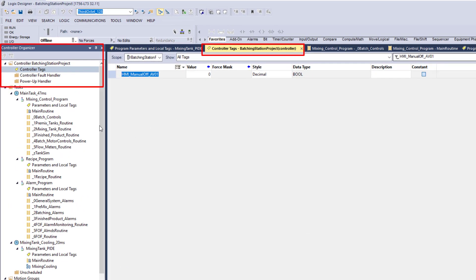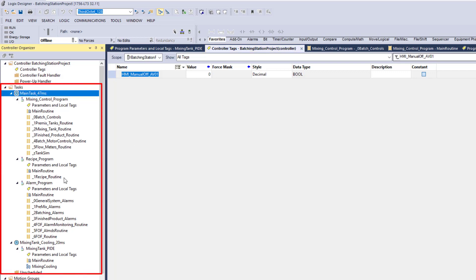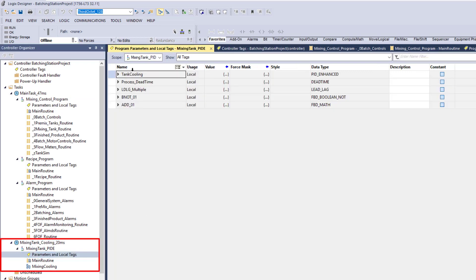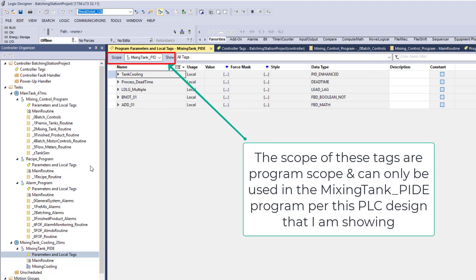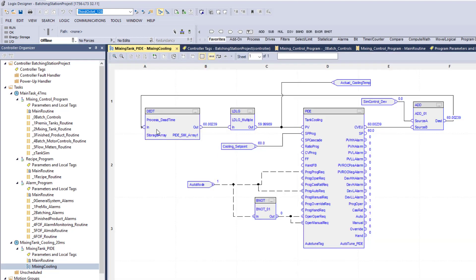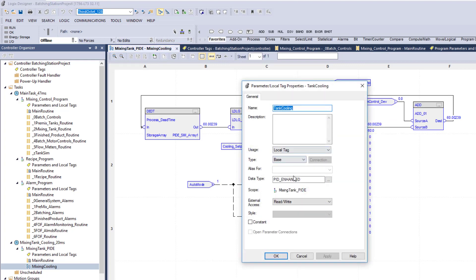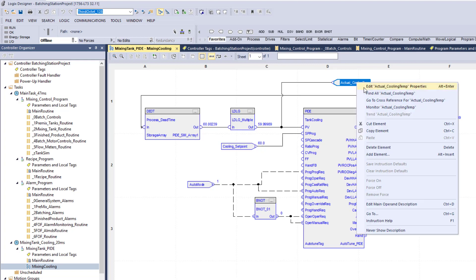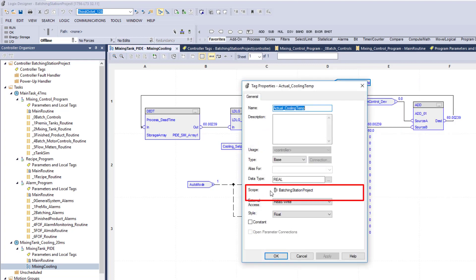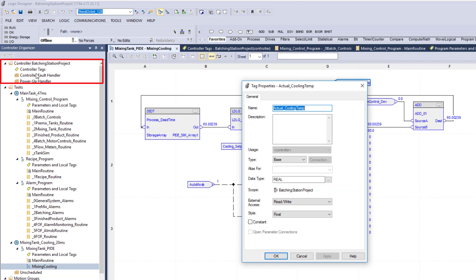The reason I'm using controller scope tags is because I can use them globally through whatever task I choose. There are instances where people use program scope tags for the simple purpose of keeping things locally used inside of that specific program. Down here in mixing, I'm using program scope for tank cooling and process dead time. This shows the scope is the mixing tank underscore PIDE.